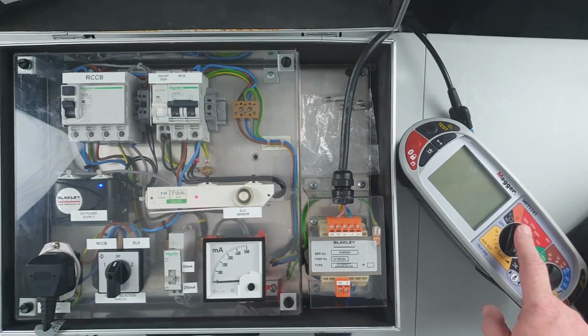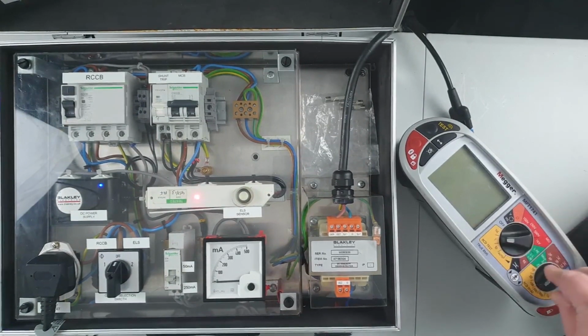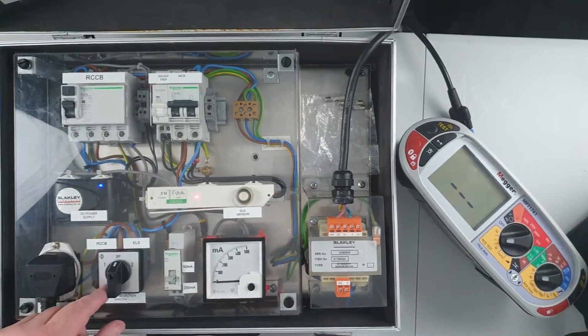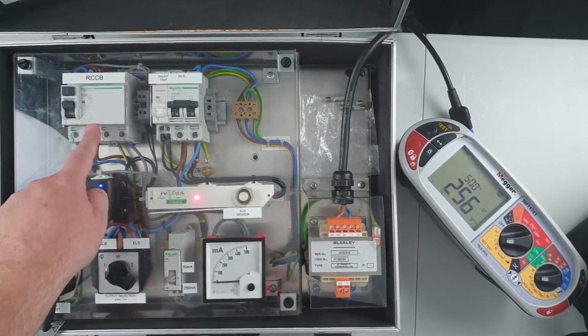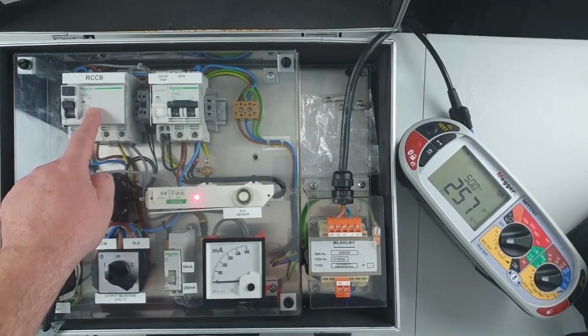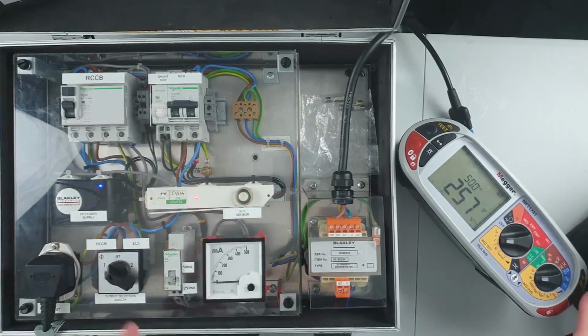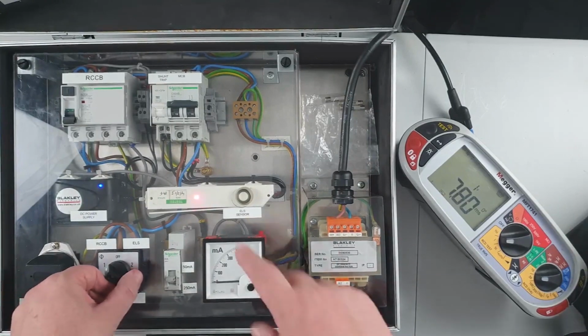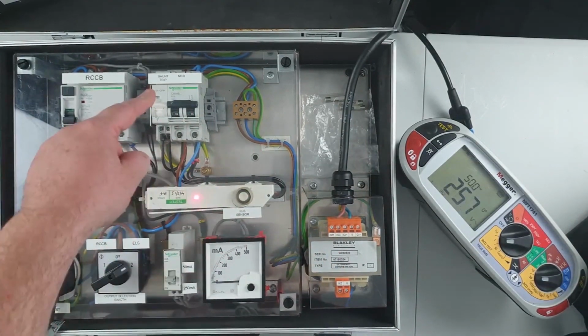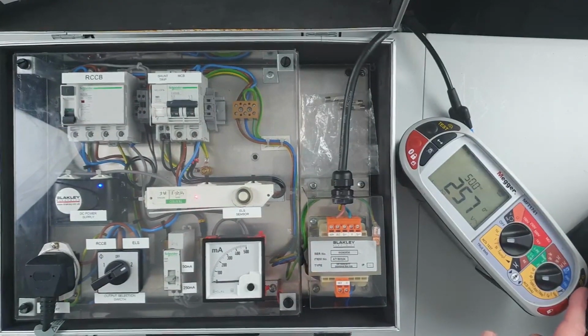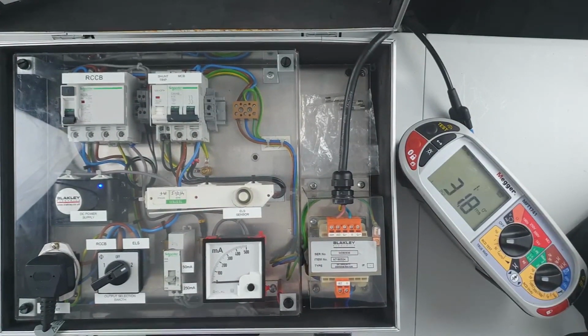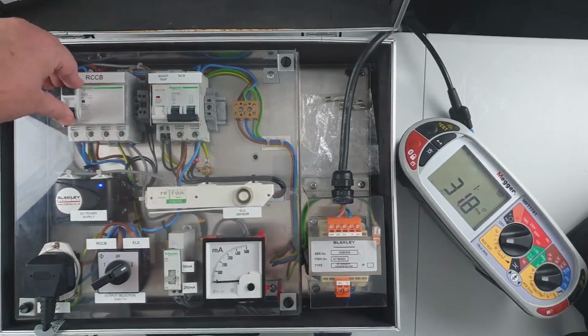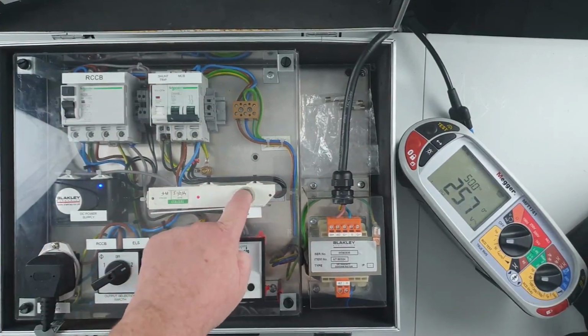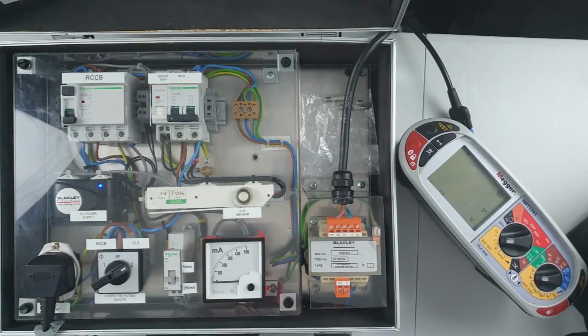Using the MFT1741 from Megger, I will set this to RCD, 30 milliamp, and we'll first of all test this RCCB here, 30 milliamp AC. So we'll test that. It trips in 7.8 milliseconds. We'll go over to the earth leakage sensor in this shunt device here. We test that one, and it trips as expected, 31.8 milliseconds. Both of these also functionally operate as expected.